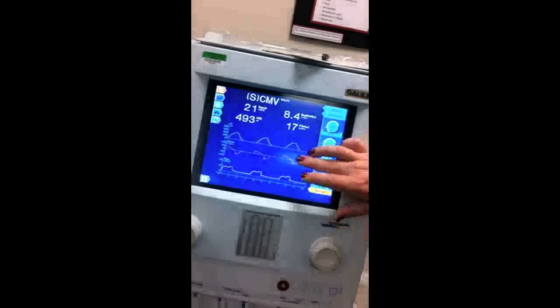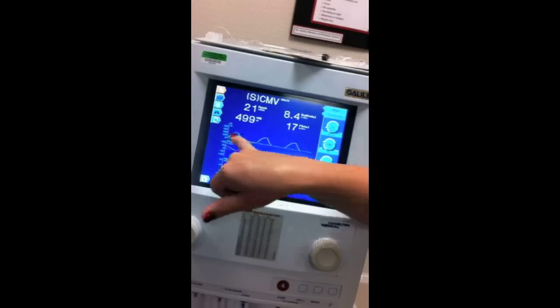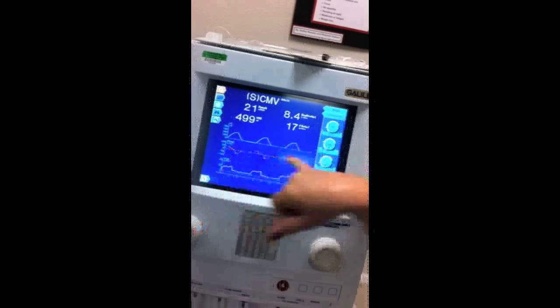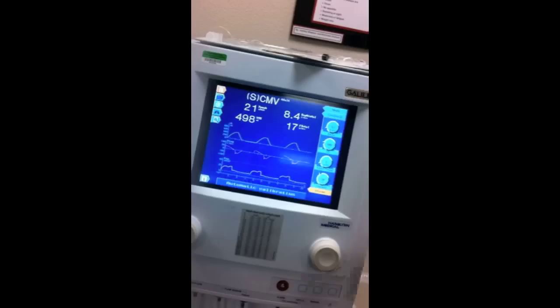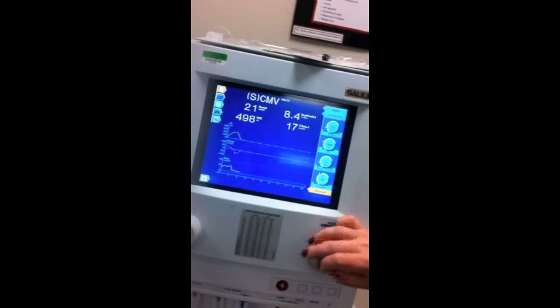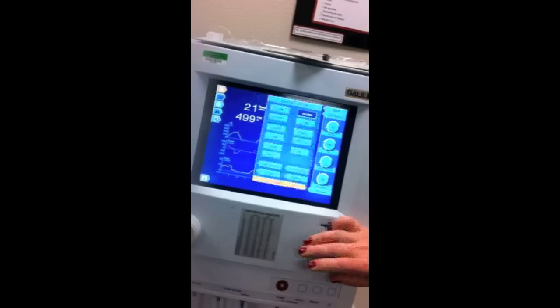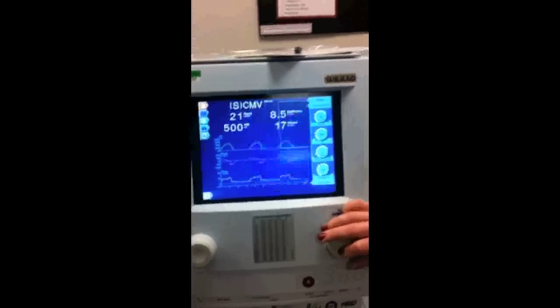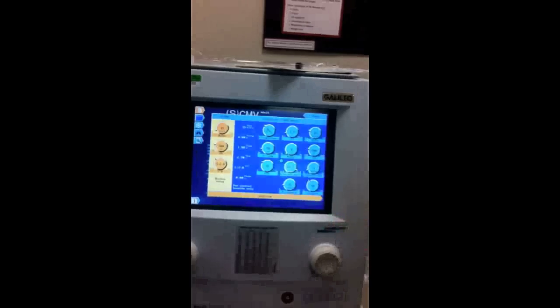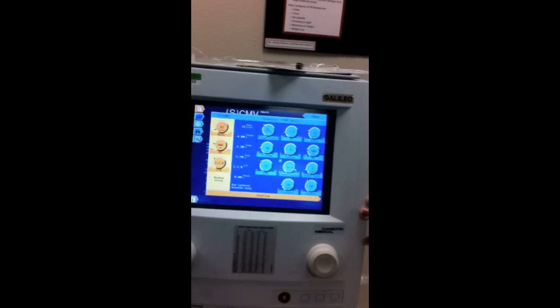On here is our waveforms like we started talking about today, so you guys can really pay attention to these. Here's our volume, our flow, and our pressure. And then I'm going to go to SIMV so I can show you. So we go to SIMV, then another screen comes up. If you do not confirm this, it won't actually change to SIMV, so just like all the ventilators, changing mode requires extra confirmation. So we're in SIMV now.